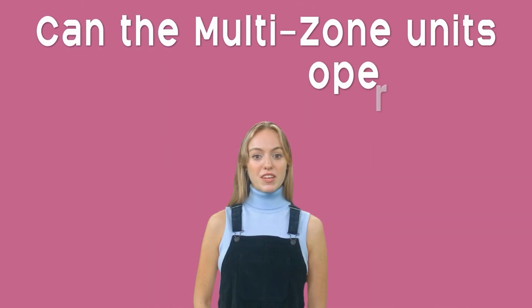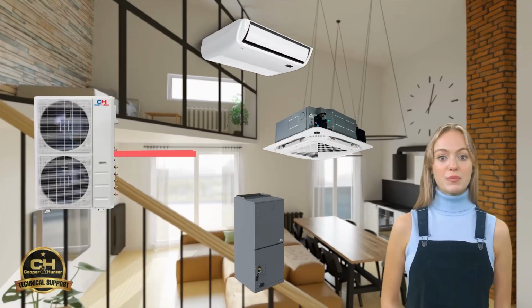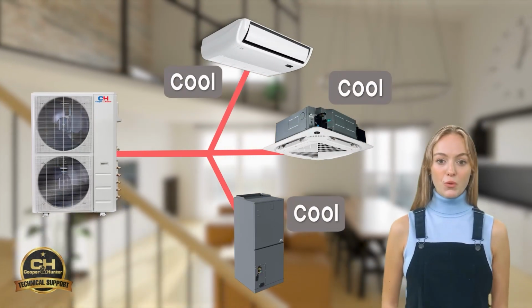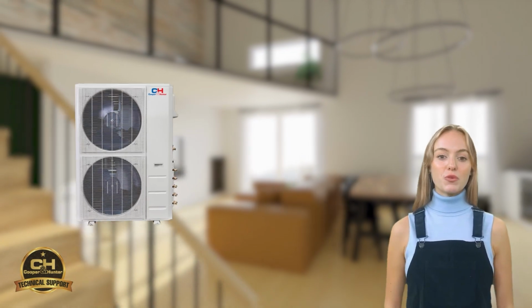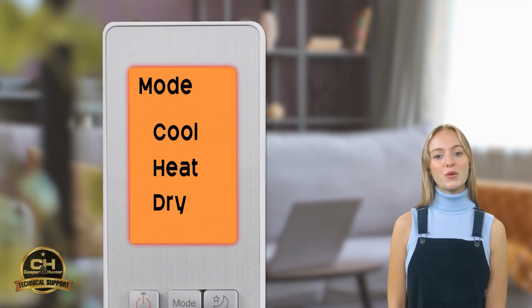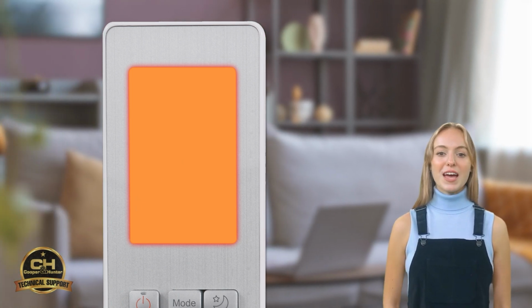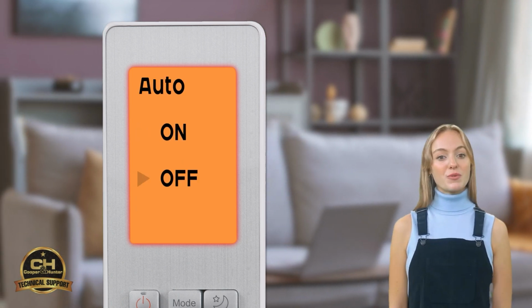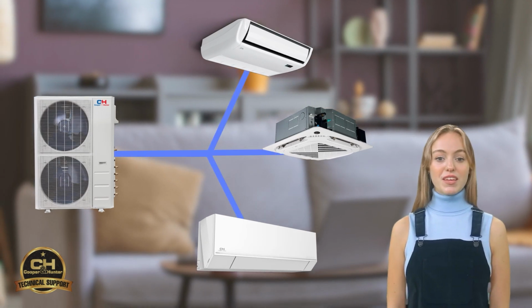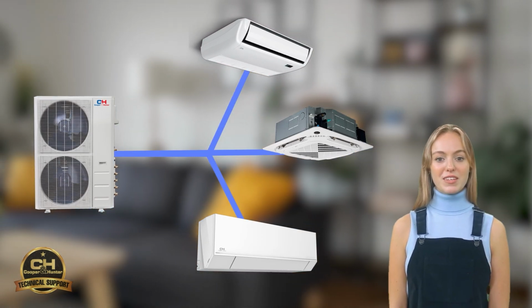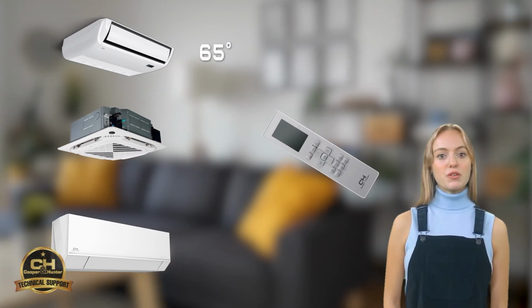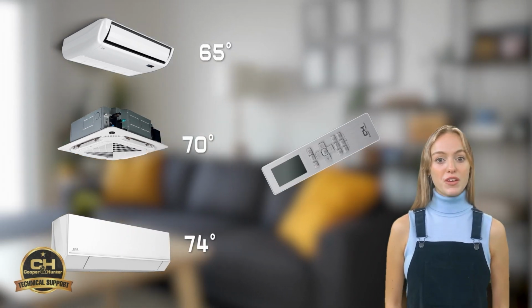Can the multi-zone units operate on different modes at once? All the indoor units connected to the same outdoor unit need to be set to the same mode of operation. This is because the outdoor unit controls the refrigerant flow and temperature according to the mode selected by the user. You can choose from cool, heat, or dry modes, depending on your preference and comfort level. However, auto mode will not work with multi-zone systems, as it may cause conflicts and inefficiencies in the system. You can still set different temperatures within the same mode for each indoor unit, as long as they are within the allowable range for that mode.